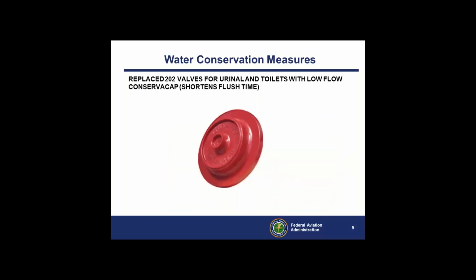And here's one of our conservation measures we used. First off, when we started this here in Oklahoma, our water rates are not as high as probably other states. We're paying about $5.50 a K-gallon. So when we replace fixtures or urinals or toilets, it's not cost effective to just replace the whole fixture. So we went ahead and just used the Conserva Cap for 202 of our valves in our facility, and it reduced it from, I believe, a 2.5 to 1.6. So we've used this sort of a flush valve diaphragm to where you can conserve water.